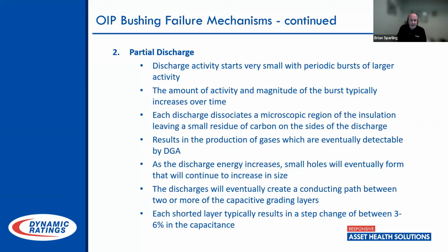The danger side of this is that this PD activity does produce gas. It does eat away at the layers of insulation inside the bushing itself. And as discharge increases, energy increases. Small holes will eventually form and continue to increase in size. And it begins to short out the layers of the condenser inside the bushing itself.